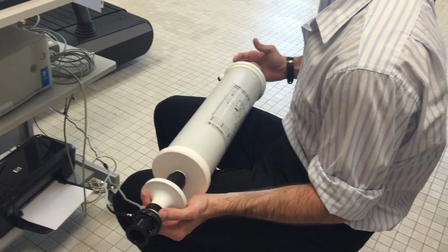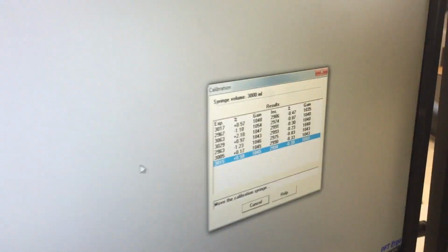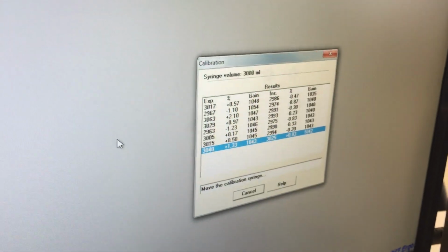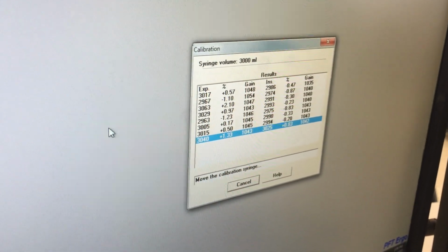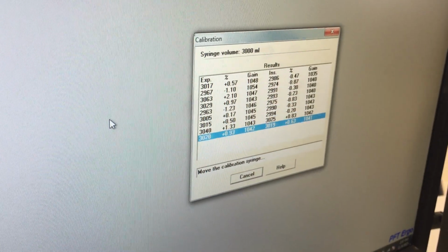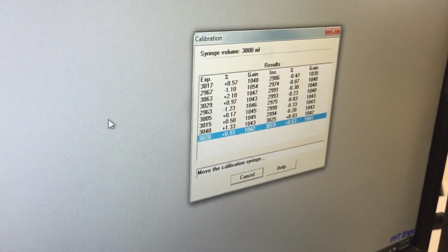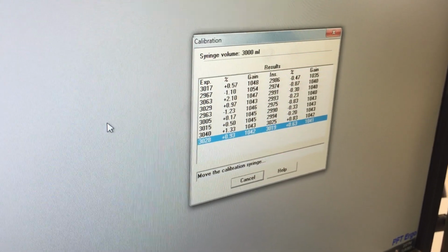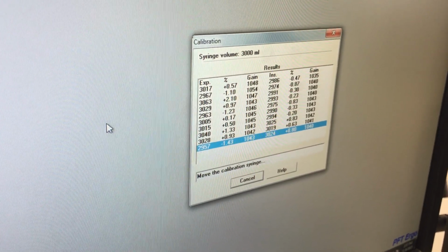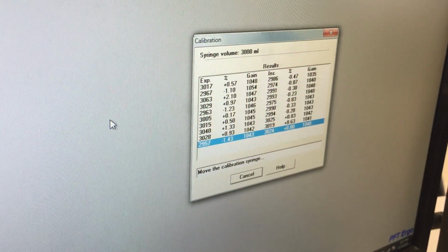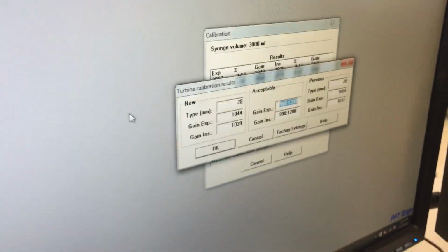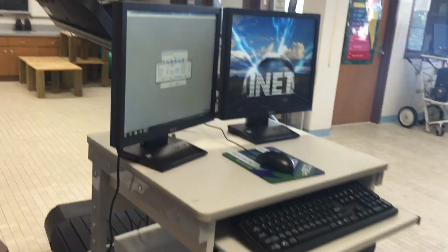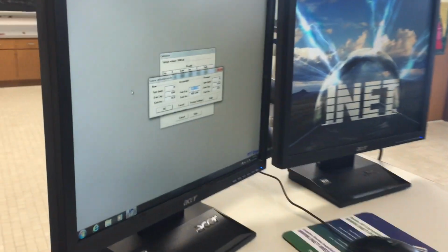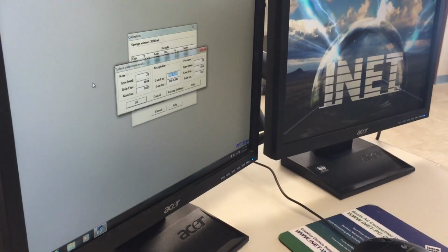After about 8 to 10 strokes, if you've kept consistent, if you've kept within the ranges, then it will automatically move forward. So at this point, you just keep pumping, nice and controlled, until the numbers are all pretty close here, maybe 1 or 2 more and we should be okay. There we go. Okay, good. After a while, if your numbers aren't close, it won't move forward to the next screen. It will move forward automatically when you've been consistent enough for the calibration to take place.